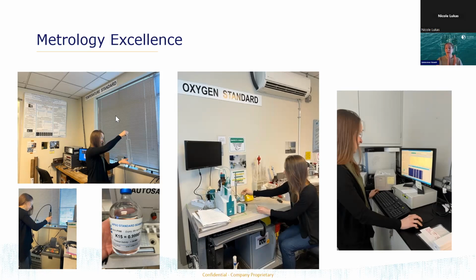So we put it in a little oven, and essentially what happens is it will heat up, and then as it's changing phase, as it's going from a solid to a liquid, the temperature plateaus, and it plateaus at 29.7646 degrees C, which again is super useful because we're really looking at things from -2 degrees C to 35 degrees C. So anything in that range is helpful for us. So now we've got two solid points. But we only have two. So how do we get all the rest of the points?